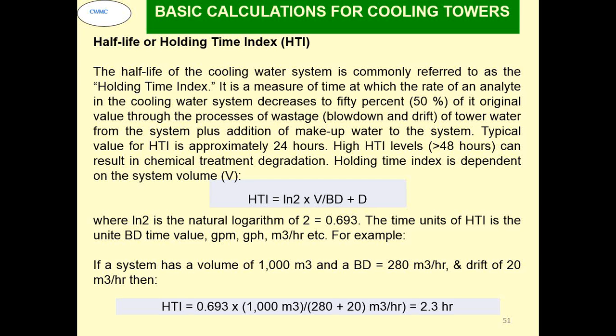Half-life or holding time index. This is the time in which the chemicals present in the water are reduced to half, or alternately, half of the water is replaced by fresh water. That is what is known as the holding time or half-life time. It is calculated as HTI equals ln 2 times V divided by blowdown plus drift, where ln 2 is the natural log of 2, about 0.693, multiplied by the holding capacity of the system divided by blowdown plus drift.